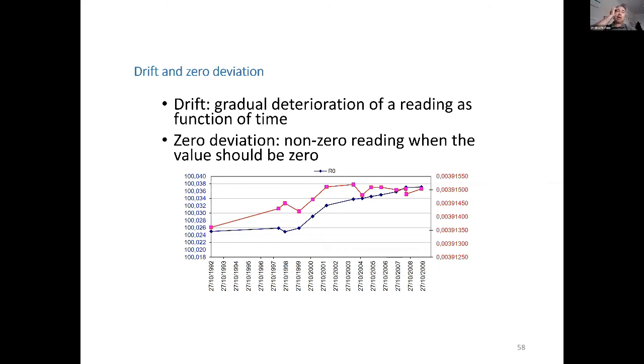I give you a very easy example of drift. The salt attack on electric contacts. The more you stay close to the sea, the more some of your instrumentation may change a little bit. It changes what? It changes the resistance, it changes the conductivity. The data logger is reading something as it did when it was brand new, but actually the salt is causing something to your electronics and electric contacts. This causes a slow drift.